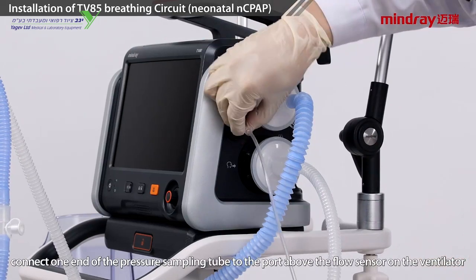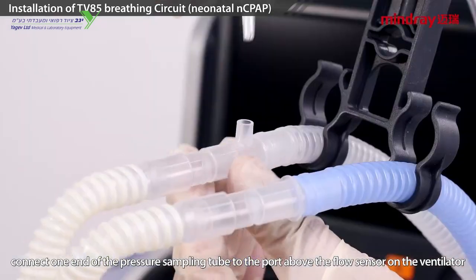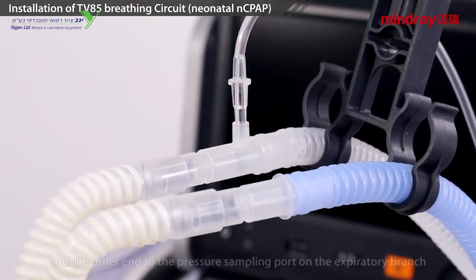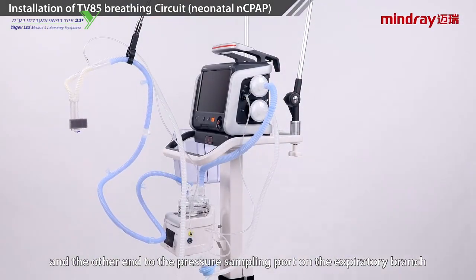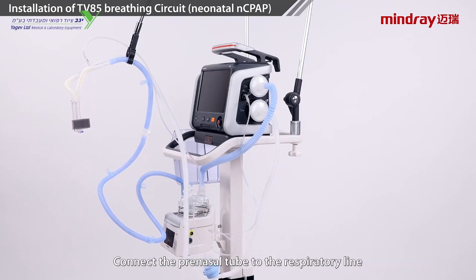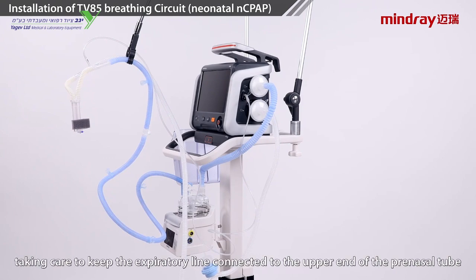Connect one end of the pressure sampling tube to the port above the flow sensor on the ventilator and the other end to the pressure sampling port of the expiratory branch. Connect the prenasal tube to the respiratory line, taking care to keep the expiratory line connected to the upper end of the prenasal tube.